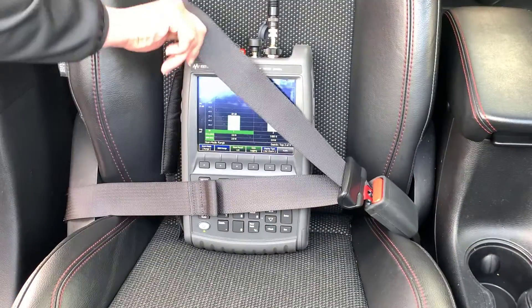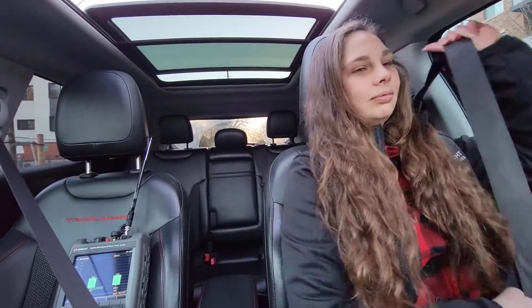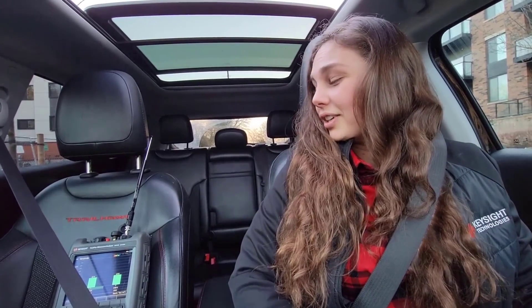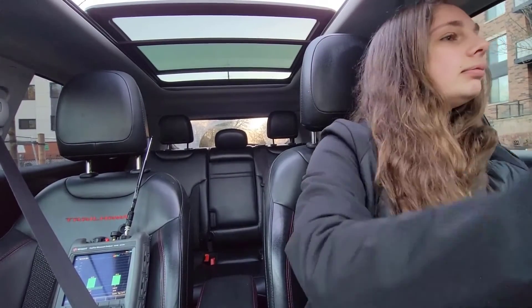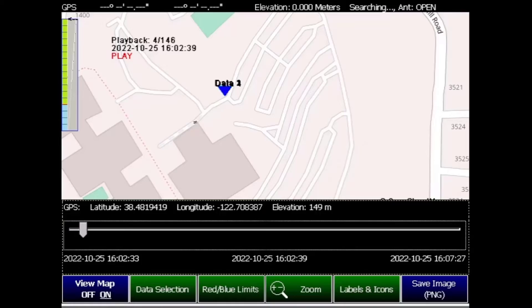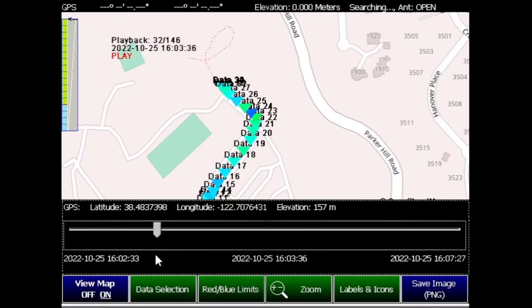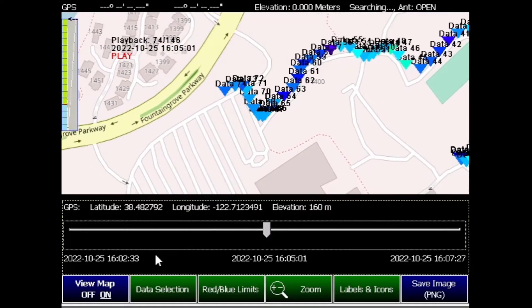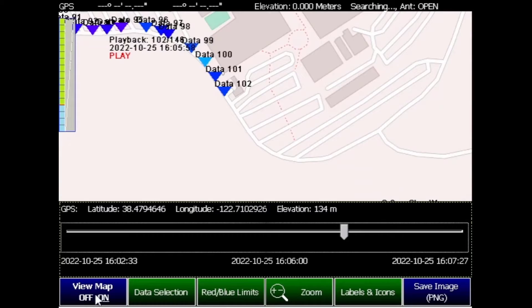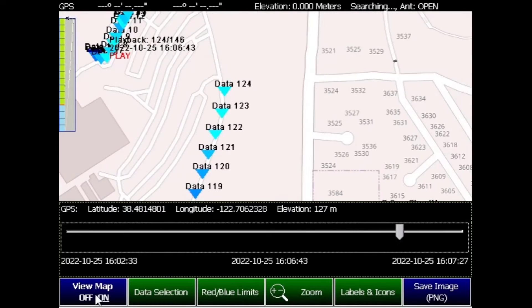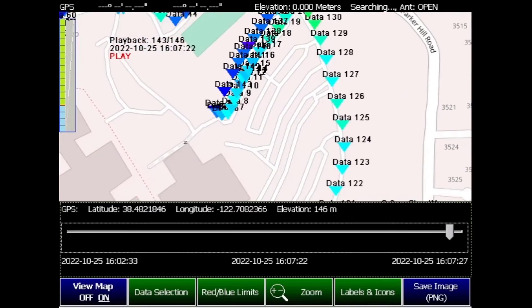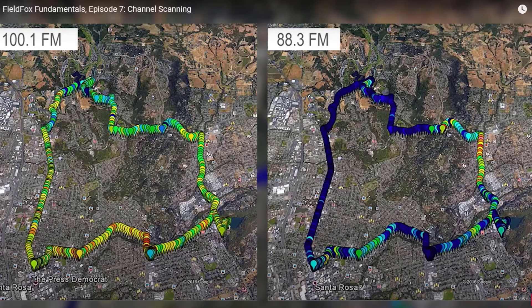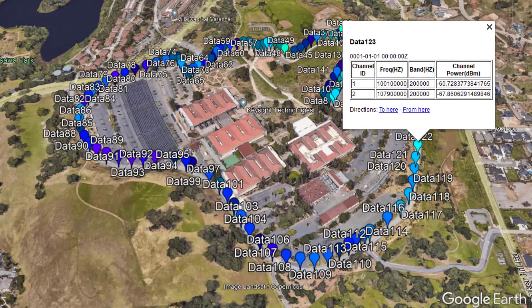Safety first! As I start driving, you can see the power levels start to change. These are recorded on a scale from deep blue to dark red — the GPS pins get warmer as power level increases. You can see the power levels of Channel 1 are consistently higher than Channel 2, but these are all within our acceptable limits of negative 80 to negative 40 dBm. Here is a side-by-side example of two channels on a drive throughout the entire city. You can see how this tool could help visualize coverage tests and identify areas with interference issues.